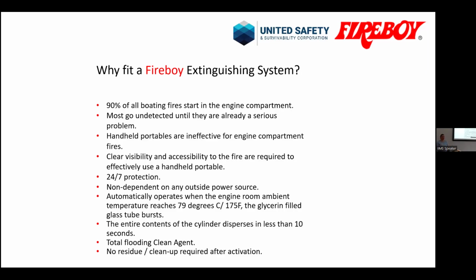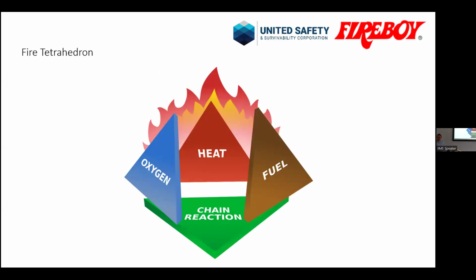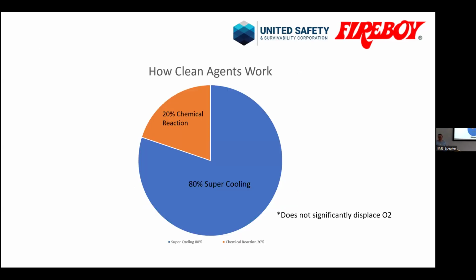The good thing with the clean agent is that it doesn't have to be pointed at a hazard. It's fitted somewhere in the protected space. It discharges all of the contents in under 10 seconds. It puts out the fire not by displacing the oxygen. The agents we use, the clean agents, are HFC 227 or Novec, well, brand name Novec, but it's FK 5-1-12. They're both clean agents. They do not displace oxygen. They are basically fighting the fire by cooling and breaking the chemical reaction within the fire.